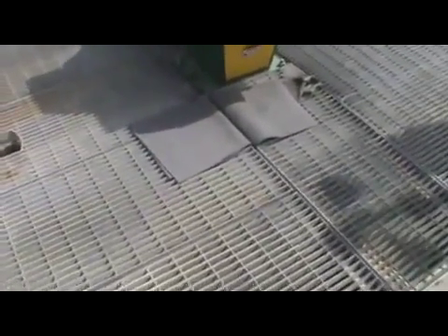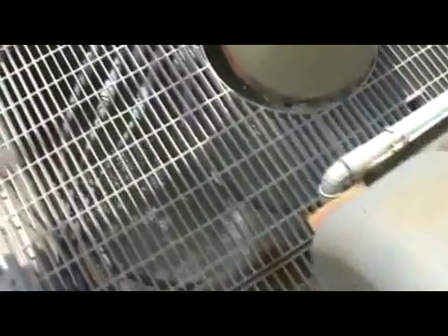You need 30 seconds for enough contact time for this stuff to bash together, but if you take too long here, the floc is going to get mixed too vigorously, and could actually start to break apart. So I'm actually standing right on top of the flash mix, and you can see right in here is where the water is coming in, chemicals are added, everything's getting mixed together.